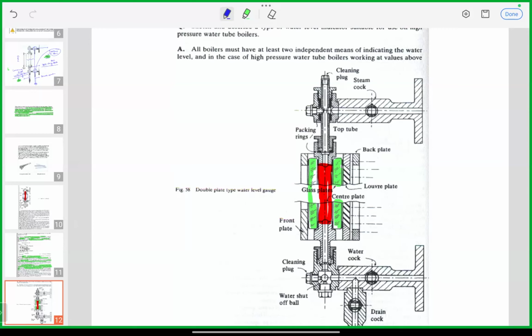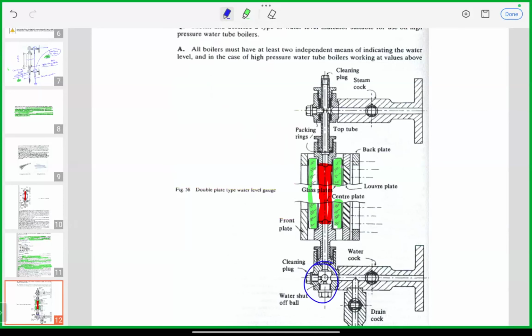So the question was about the workshop, like how we will assemble and reassemble, that's what needs to be done. You require to check the condition of the back plate, check the condition of your glass, check for pitting marks, wire drawing, any physical damage. For the valves, these cocks are required to have their sealing changed - graphite seals are there, these seals are required to be checked. If you have plugs, make sure the plugs are properly tightened. That is general inspection, nothing very special about it.